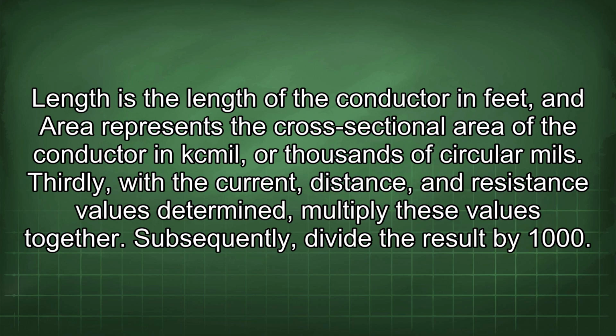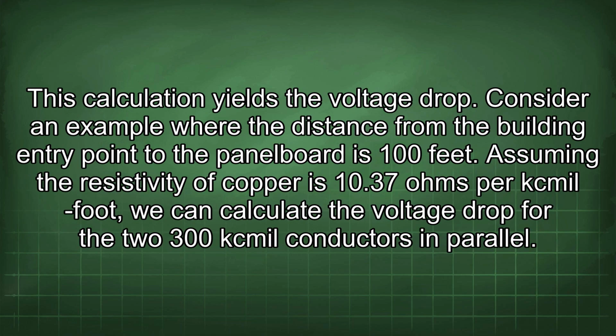Thirdly, with the current, distance, and resistance values determined, multiply these values together. Subsequently, divide the result by 1000. This calculation yields the voltage drop. Consider an example where the distance from the building entry point to the panel board is 100 feet. Assuming the resistivity of copper is 10.37 ohms per kcmil foot, we can calculate the voltage drop for the two 300 kcmil conductors in parallel.